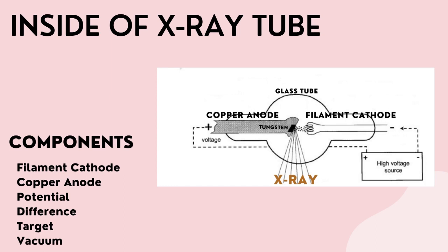The filament cathode is functioned to emit electrons. The copper anode is to hold the target. The potential difference across the tube is very high to ensure electron generation, while the target is the place where electrons will collide and produce x-rays. The tube is vacuumed to ensure that the accelerated electrons move without colliding with air molecules.